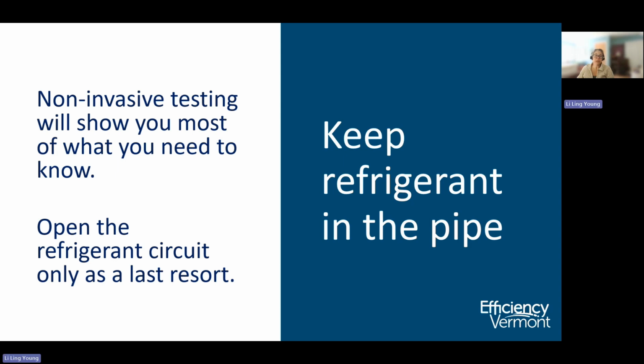Anytime you attach gauges to a line set, some refrigerant will be lost. And even worse, you risk introducing moisture and debris into the refrigerant. Don't attach gauges to the system unless you know that only measuring the refrigerant pressure is going to solve the problem. The alternative is non-invasive testing.